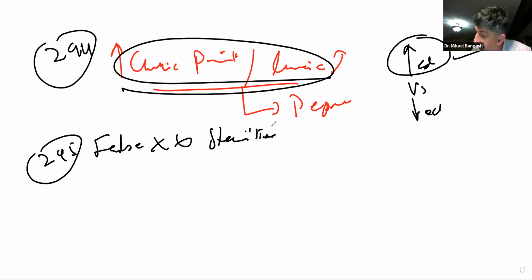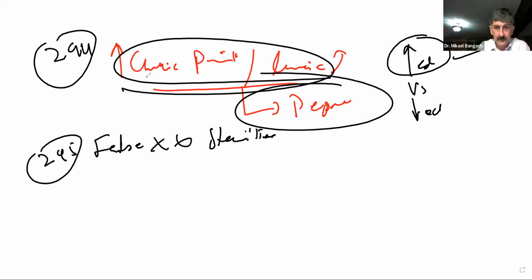Most transducers simply require disinfection as they do not penetrate mucous membranes. What did I say yesterday? And even if they do, they will be covered up with probe covers, right? Or some sort of covering. Sterilization could depolarize the PZT. That's what we just said. That's true as well. They are unlikely to transmit infection. Yes, mainly because if they come across mucous membranes, they are covered up with a probe cover. And if you use it on the surface of the body, it is going to be running on the top of the surface of the skin. And what was it that the skin was?